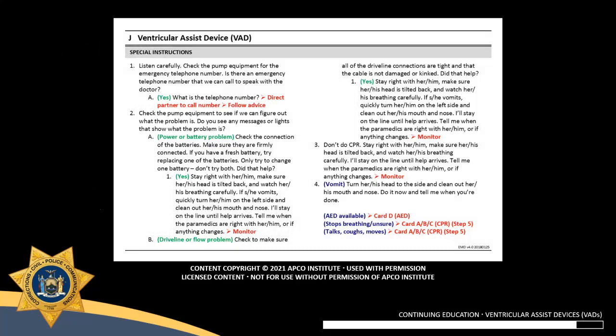But that being said, you can see we do have an EMD card protocol that we use for this kind of incident. Aside from contacting the VAD coordinator, it's some basic steps that we can tell the caller to check to see if there's any obvious or simplistic problems that we can correct with the VAD device that might be causing an issue. So, instruction 1, listen carefully, check the pump equipment for the emergency telephone number, contact the VAD coordinator. Check the pump equipment, see if the batteries are hooked up, try replacing one of the batteries with a fresh battery. Maybe check to make sure the cable isn't kinked. Maybe the cable got unplugged from the control box, whatever.